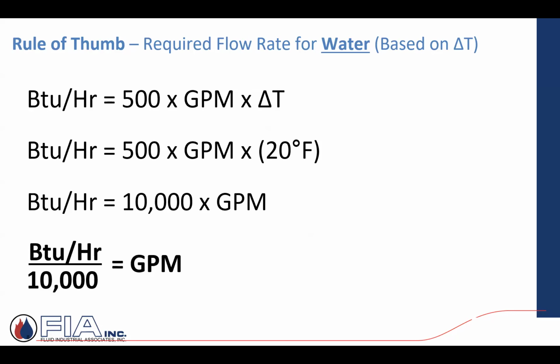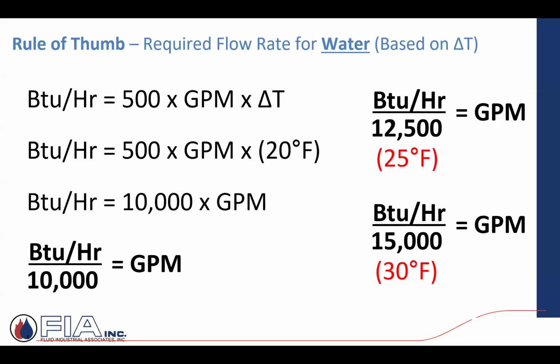A million BTUs. What's the flow rate? 20-degree drop? 1 million BTUs divided by 10,000 is 100. A 50,000 BTU load divided by 10,000 is 5 gallons a minute. A 600,000 BTU snow melt application designed on a 20-degree drop, 60 gallons a minute. So it's an easy number. It's a very easy number to work with. But just know where it's coming from with some of that formula behind the scenes.